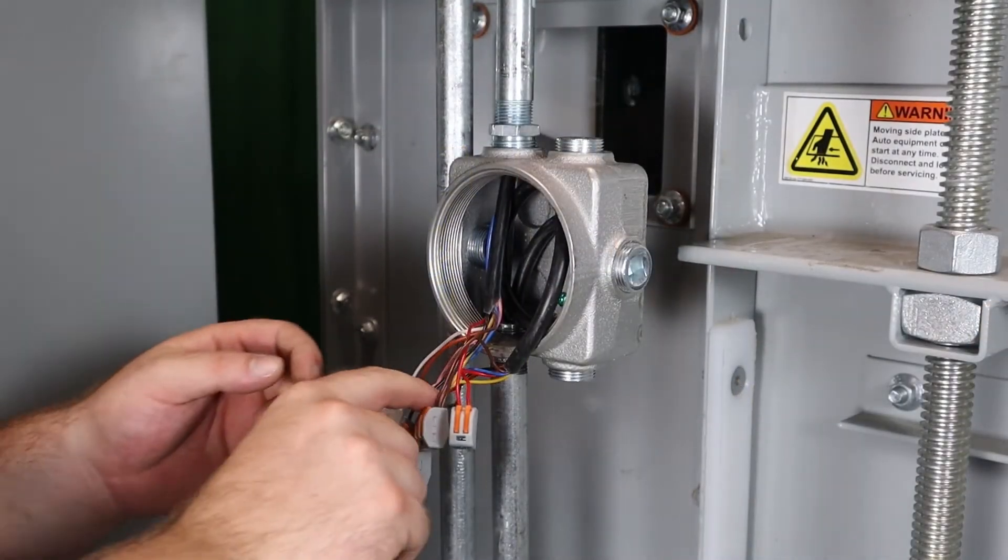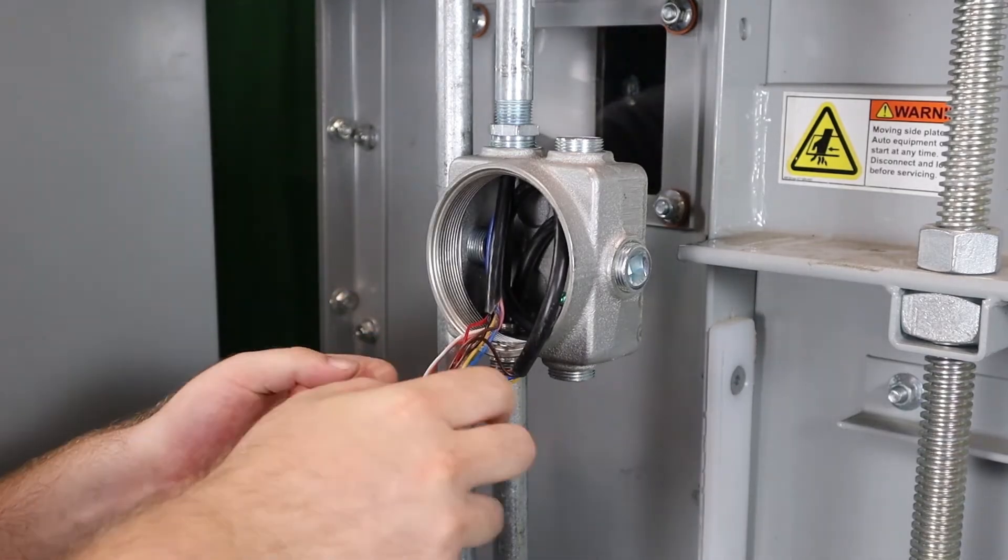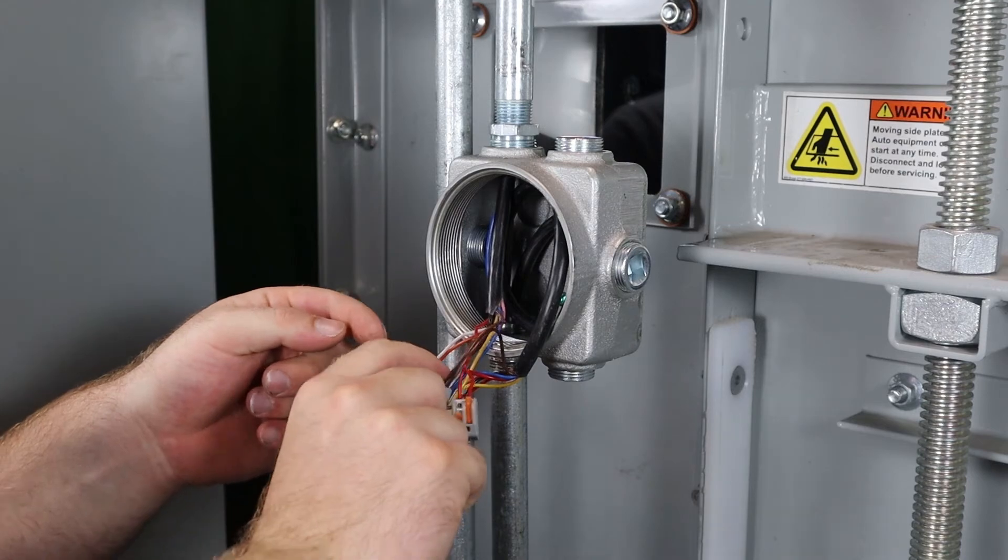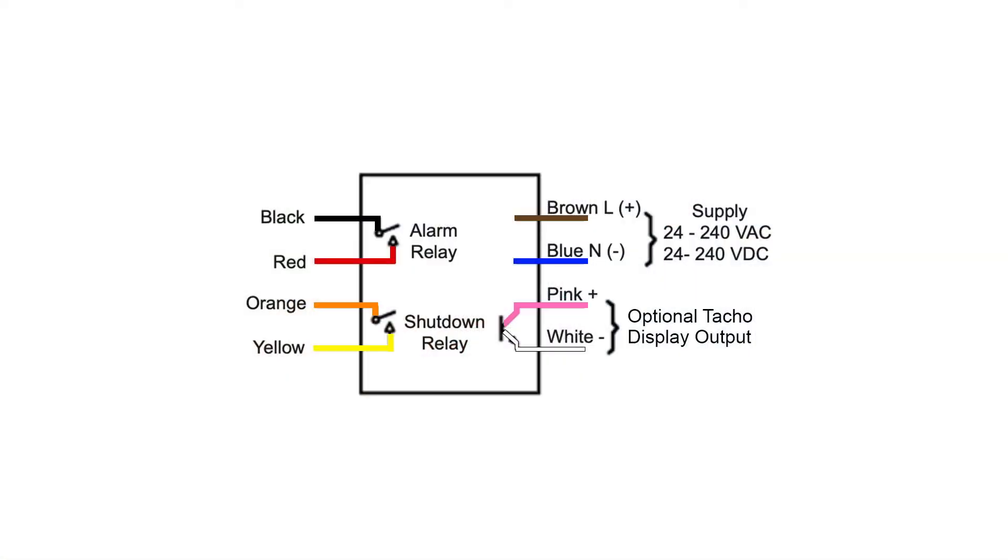Now to wire the unit up. First, connect the wires directly into the control circuit or into the plant PLC. There are eight wires on the M800: two for power, two for alarm, two for shutdown, and two for the display.